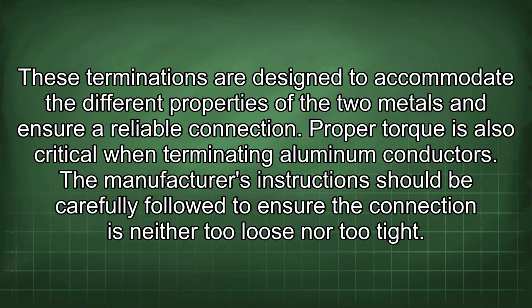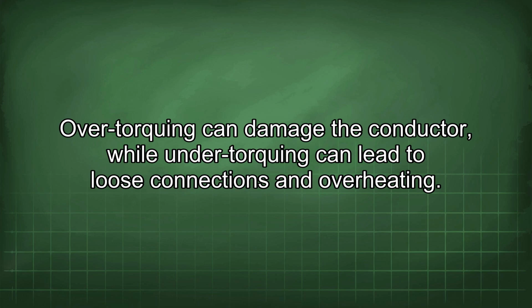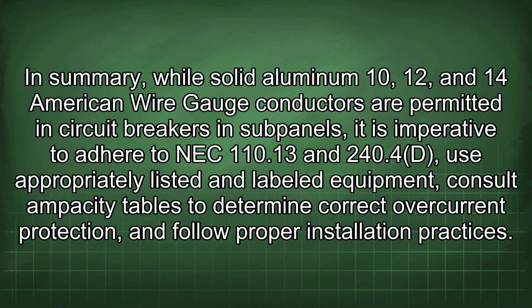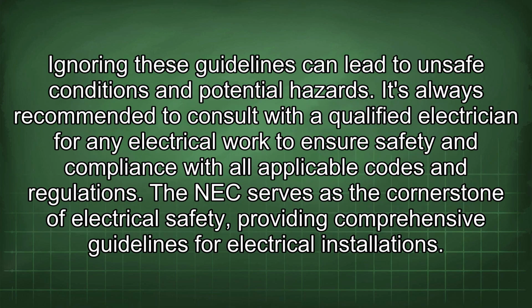Proper torque is also critical when terminating aluminum conductors. The manufacturer's instructions should be carefully followed to ensure the connection is neither too loose nor too tight. Over-torquing can damage the conductor, while under-torquing can lead to loose connections and overheating. In summary, while solid aluminum 10, 12, and 14 American wire gauge conductors are permitted in circuit breakers in subpanels, it is imperative to adhere to NEC 110.13 and 240.4(D), use appropriately listed and labeled equipment, consult ampacity tables to determine correct overcurrent protection, and follow proper installation practices. Ignoring these guidelines can lead to unsafe conditions and potential hazards.